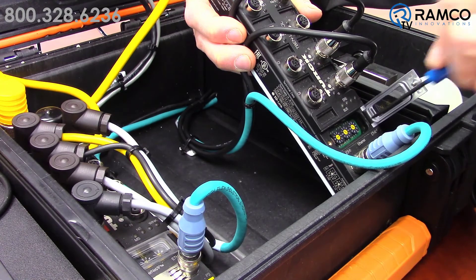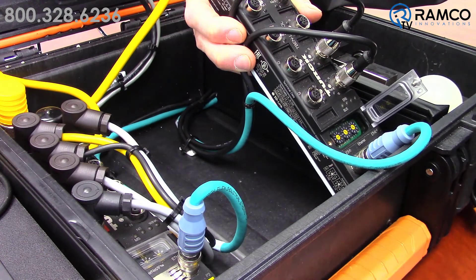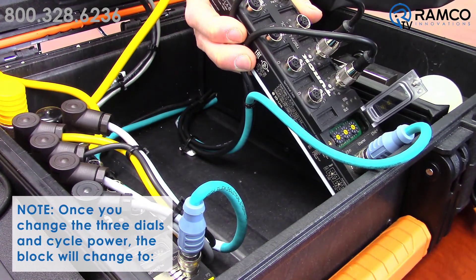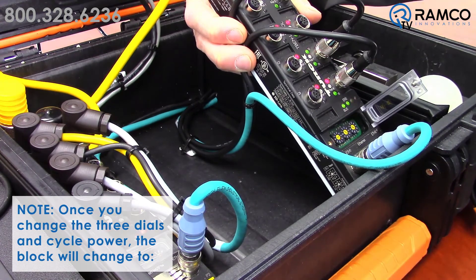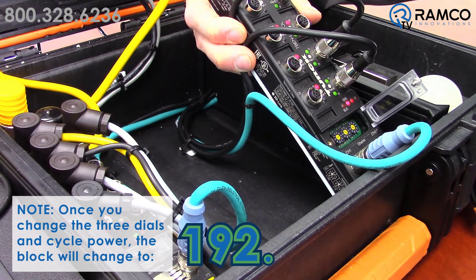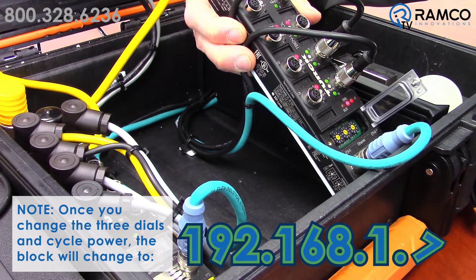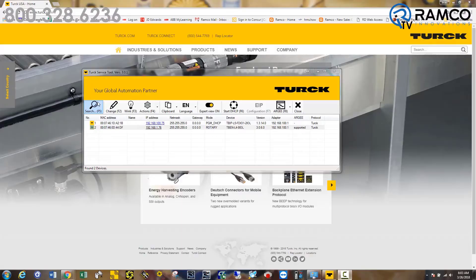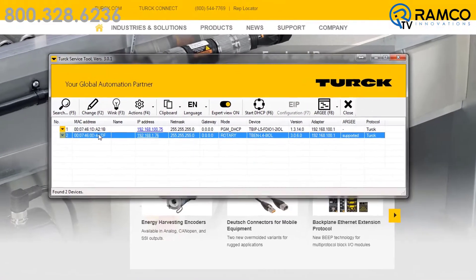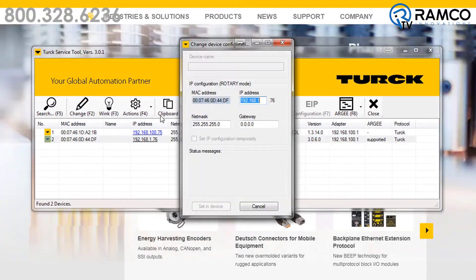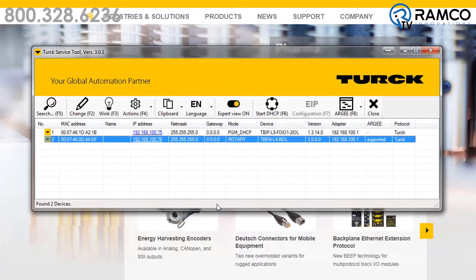For example, mine is set to 76. Please note: once you change these three dials and cycle power, the block will change to 192.168.1.76. If your PLC is on another subnet — for example, 192.168.100.76 — you will need to use the Turck Service Tool to change the first three octets to match the IP address of your PLC.